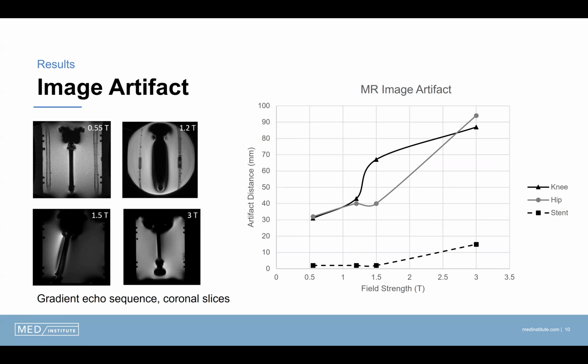The worst case image artifact for all devices occurred with gradient echo scans. An example of the worst case image artifact for the knee prosthesis at each field strength is shown in the figure on the left. The resulting artifact distance for each device at each field strength is shown in the plot on the right. These results depict that image artifact of the devices increased with increasing MRI field strength, or stayed the same as it did between 0.55 Tesla and 1.5 Tesla for the stent.